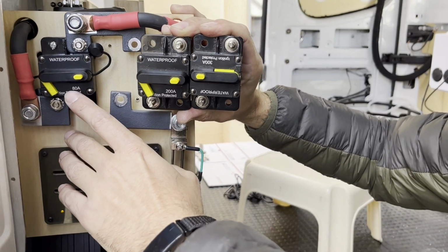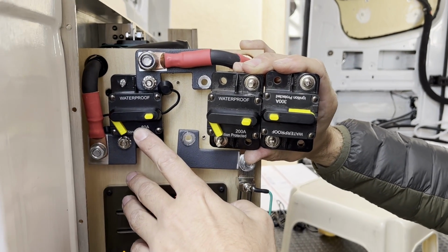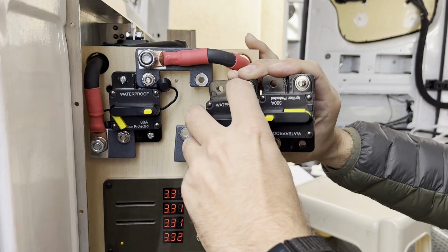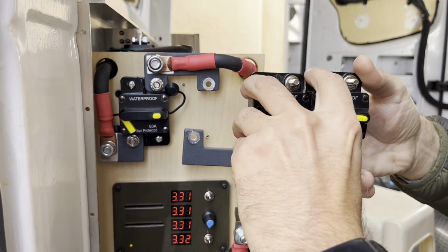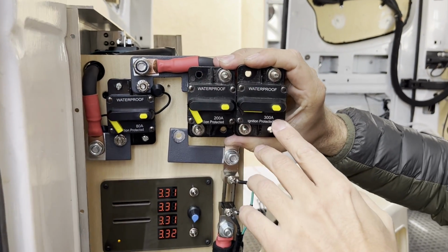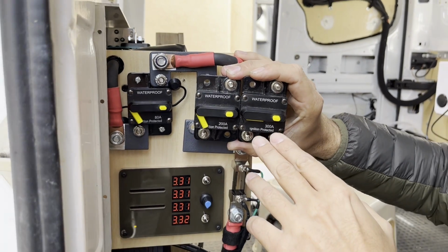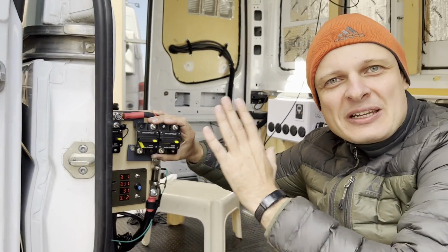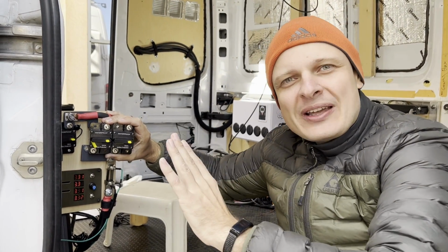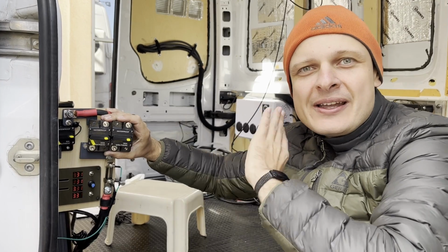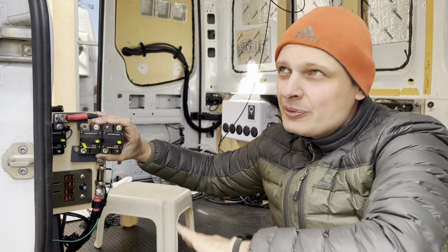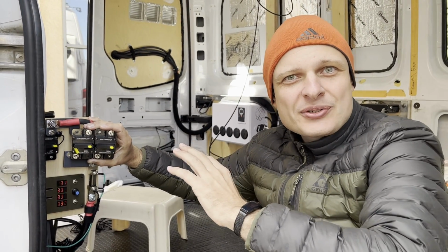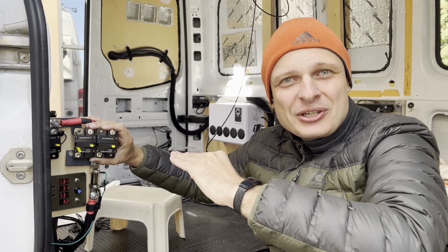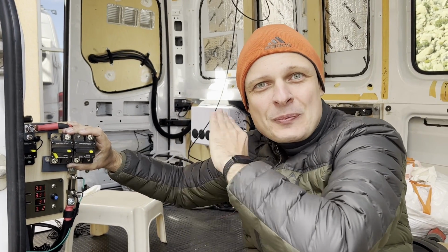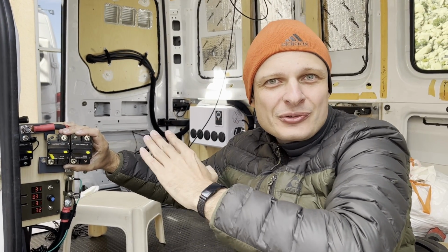These three products, the 80 amp circuit breaker, the 200 amp circuit breaker, and the 300 amp circuit breaker, they perform identical. They break exactly 4 to 5 seconds after you apply 192 amps to them. We don't have a way to apply more precise amperage to them, but the point is, at 192 amps, all three of them break after about 4 to 5 seconds.